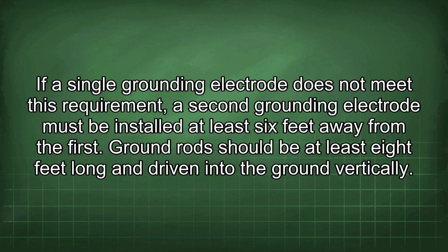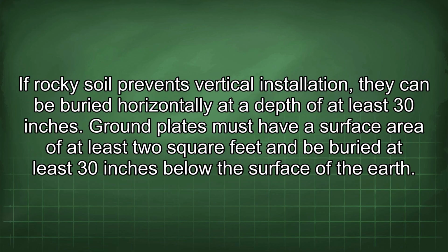If a single grounding electrode does not meet this requirement, a second grounding electrode must be installed at least 6 feet away from the first. Ground rods should be at least 8 feet long and driven into the ground vertically. If rocky soil prevents vertical installation, they can be buried horizontally at a depth of at least 30 inches. Ground plates must have a surface area of at least 2 square feet and be buried at least 30 inches below the surface of the earth.